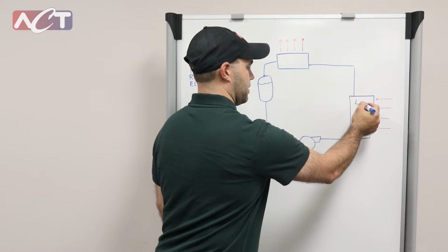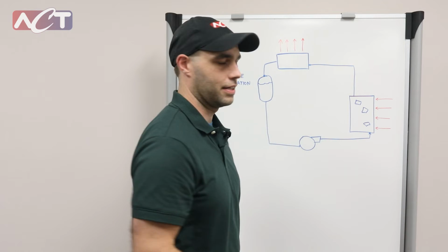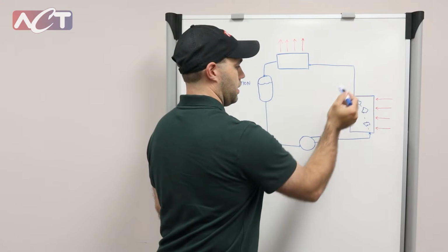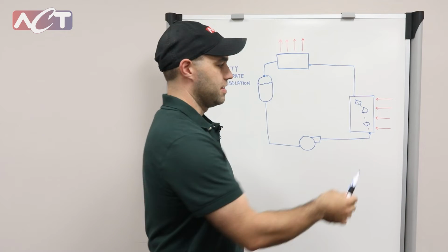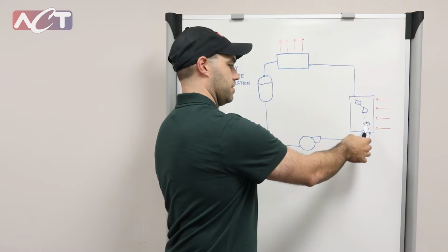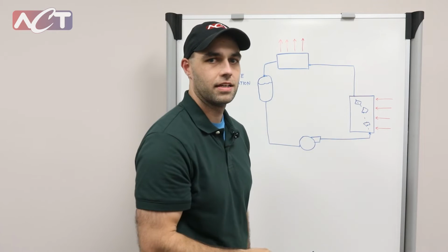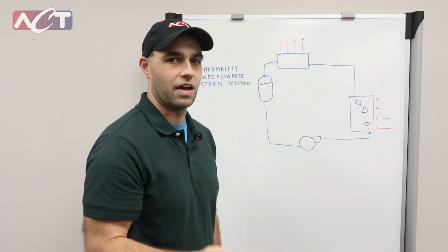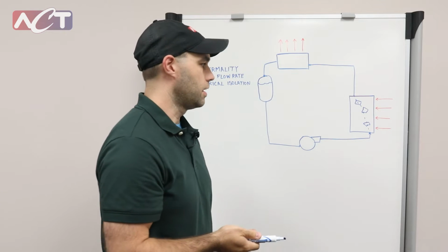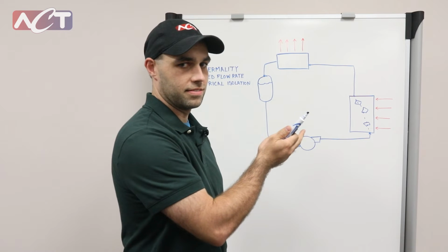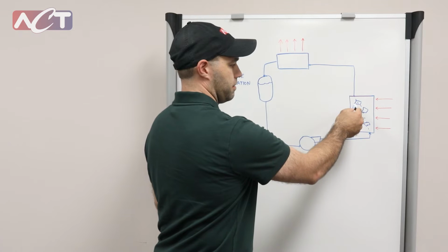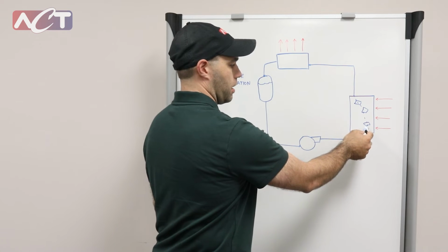And so as you have these random devices placed throughout here, as coolant moves through here, if you're using single phase, that coolant has to heat up as it takes the heat from each of these devices. In two-phase, the heat is taken by the evaporation of the coolant, and so the temperature remains constant as it goes through there.